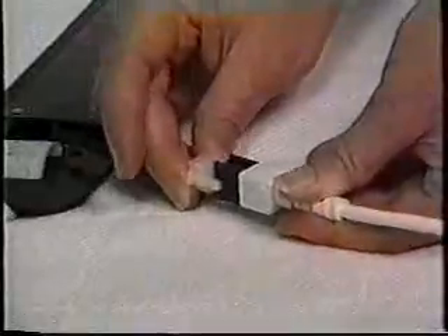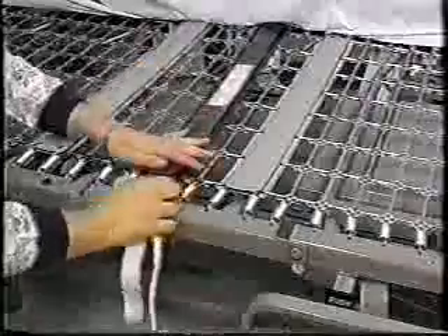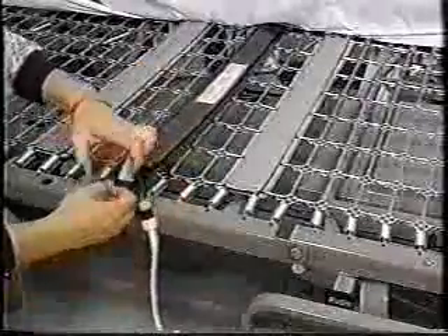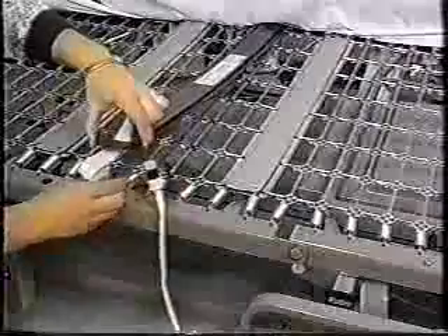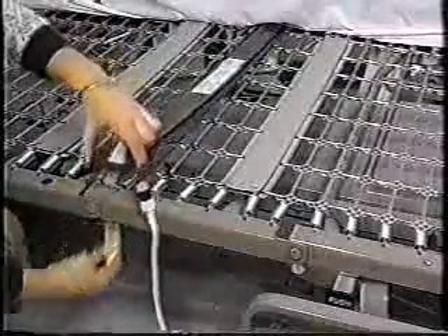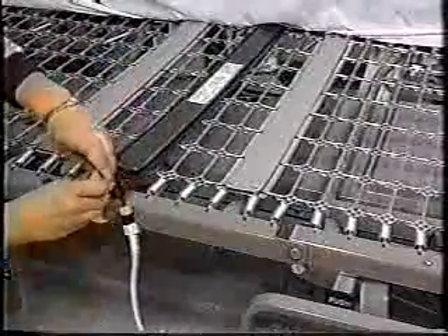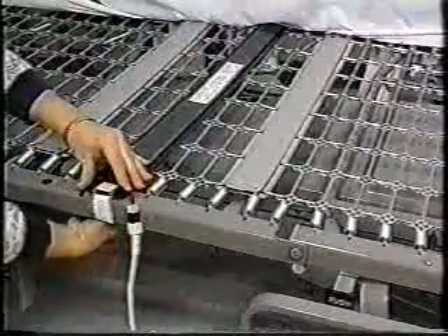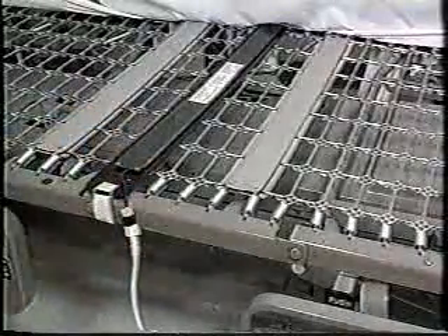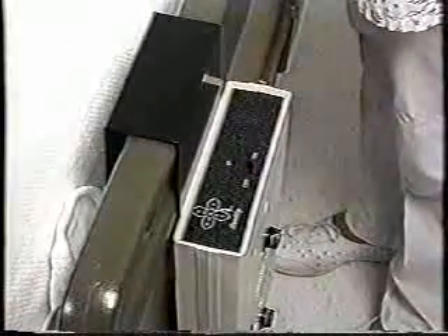Connect the sensor extension cable to the pad. Place the sensor pad under the mattress at the level of the patient's buttocks. Connect the sensor cable into the 2-sensor jack on the control unit. Test the alarm again by turning the unit on before placing the patient in bed.